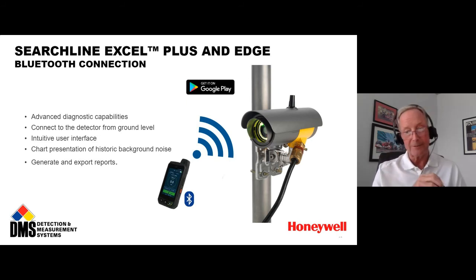Or when you're connected to the IR receiver with your Bluetooth device, it'll have a blue ring confirming that you're connected. Which, by the way, one thing I'll add about using the tablet, and again, this is speaking from experience, is that you don't have to be hands-on with the detector when you're communicating with it utilizing the functions of the tablet.